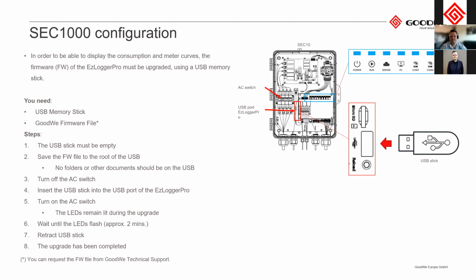It's very simple to update the firmware on these devices. You put the firmware on a normal USB stick, standard USB 2.0, you just put it on the root of the USB, so not in a folder, with the correct file name. You plug it into the side of this device, you switch the power off, you switch the power back on again, and it will automatically update. It normally takes roughly 5 minutes.